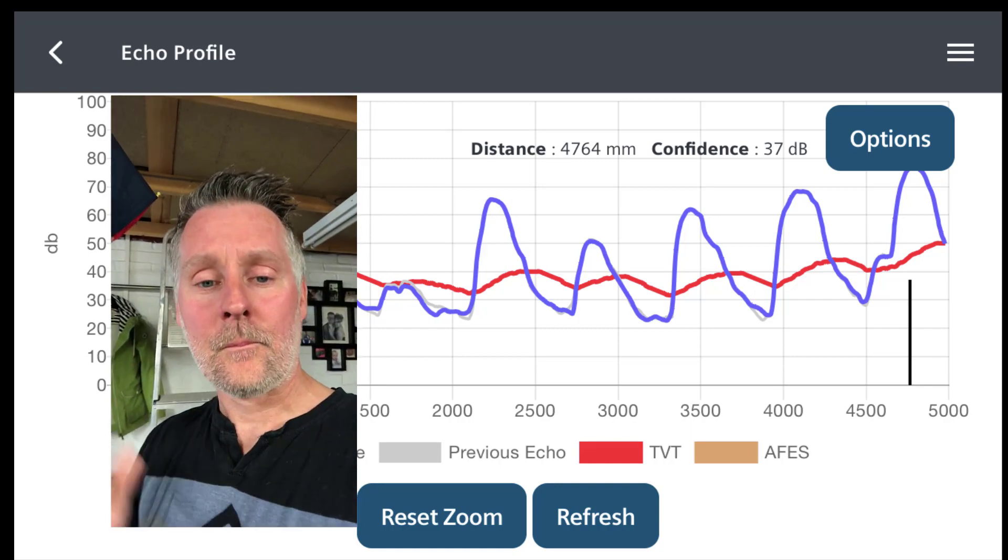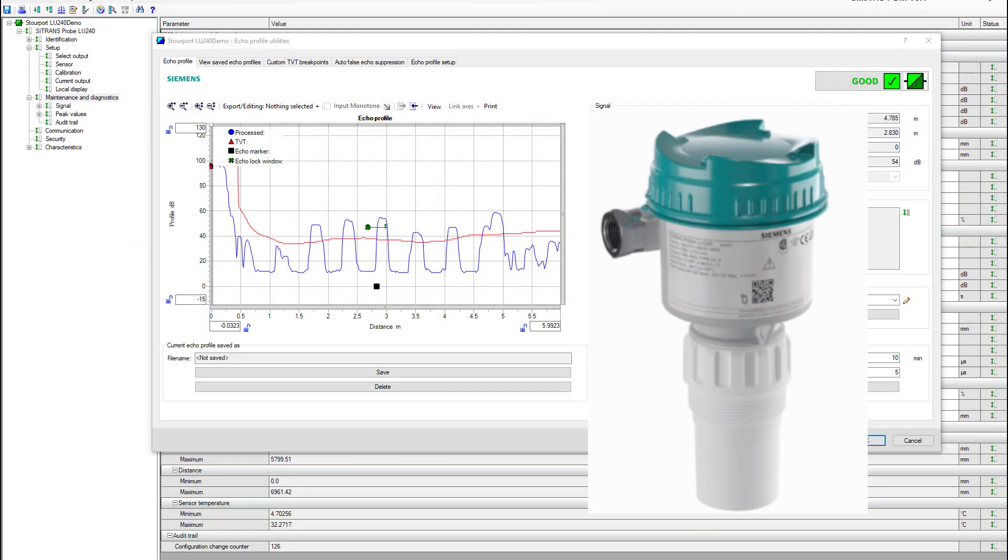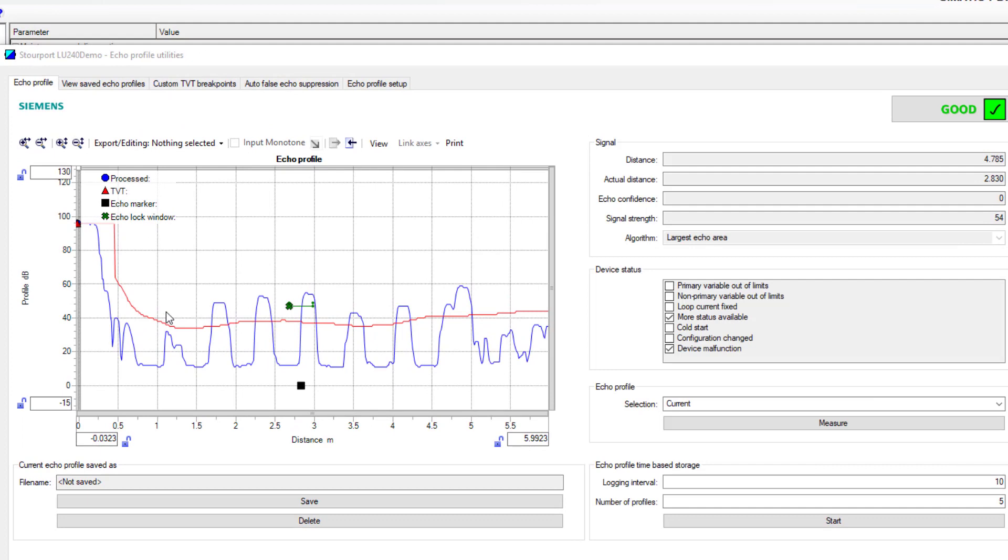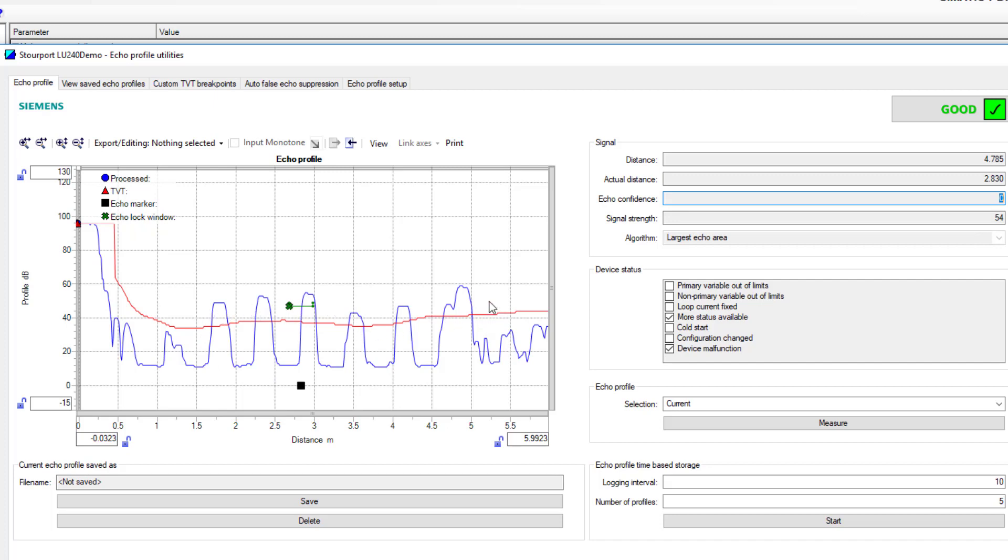We will start with the LU240 which has a 10 degree beam angle. As you can see without the obstacles, this device is already struggling a little bit. Out of the box, I have a confidence of zero but a relatively good echo strength. I would expect it really to be up in the 80s and that's because the signal is bouncing off all of these joists and it looks like I've got some shelving at the bottom of my back wall. Out of the box the LU240 needs a little bit of help, but we have to remember we do have transducers with narrower beam angles and really this is installed quite close to this structure.